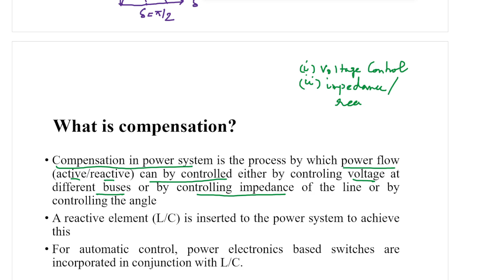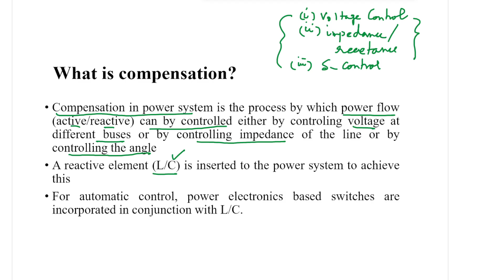By these three ways we can control or change the flow of active and reactive power. So this is the compensation — the process by which power flow can be controlled by controlling these three parameters: either voltage control, or impedance/reactance control, or delta/angle control. Now it is customary that either an inductor or capacitor is necessary to do that. An inductor or capacitor is necessary mostly, but resistance will also work; mostly inductance and capacitance will be necessary to achieve this, to control these parameters.